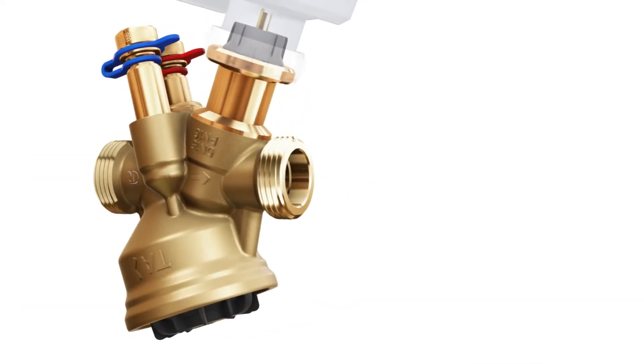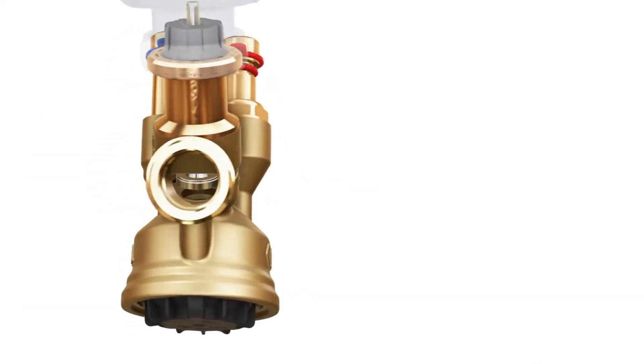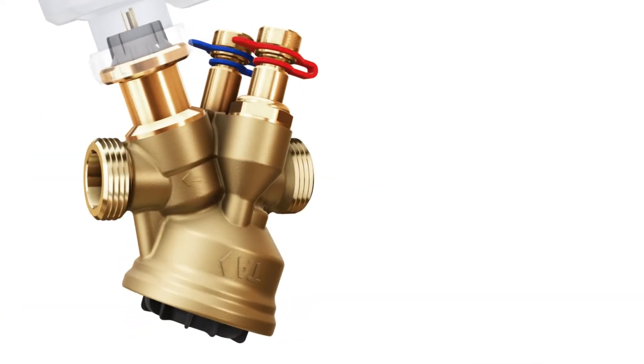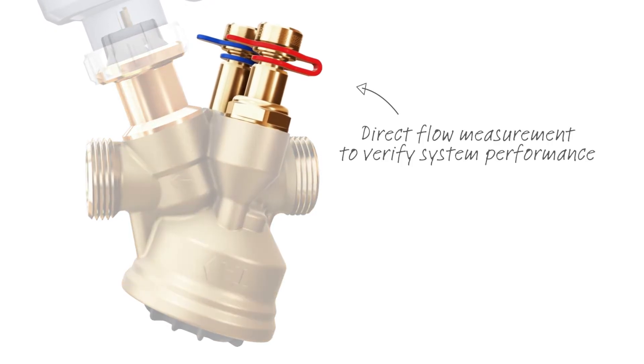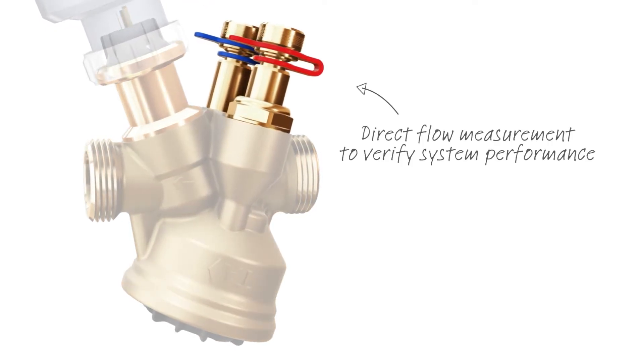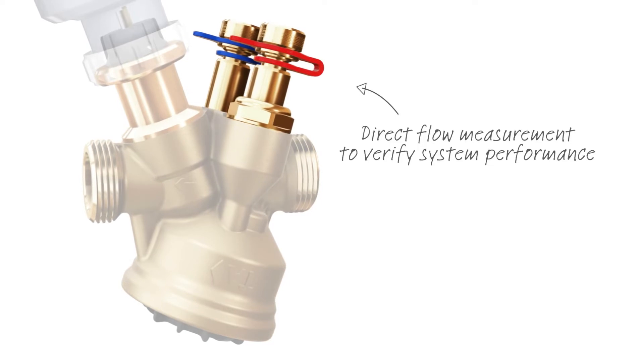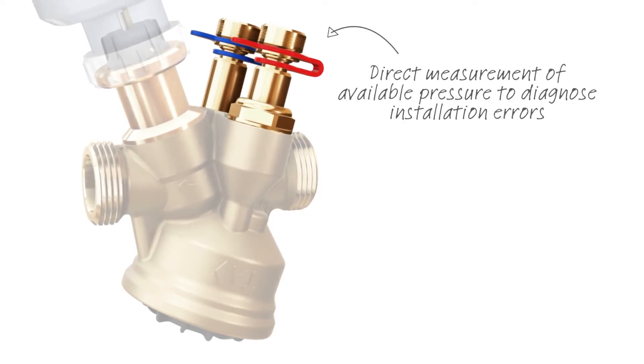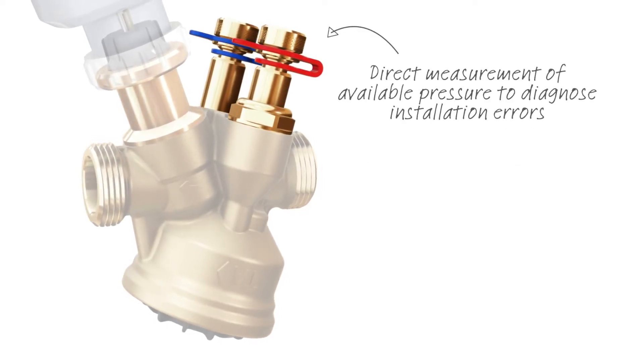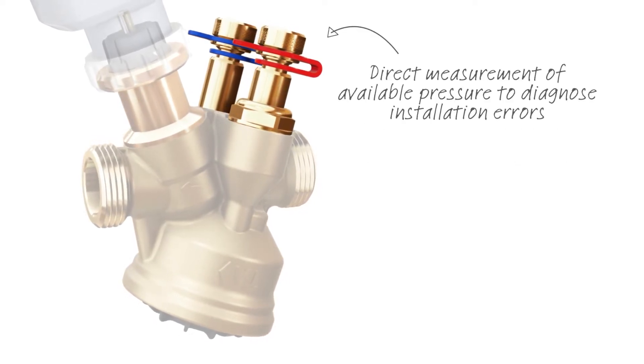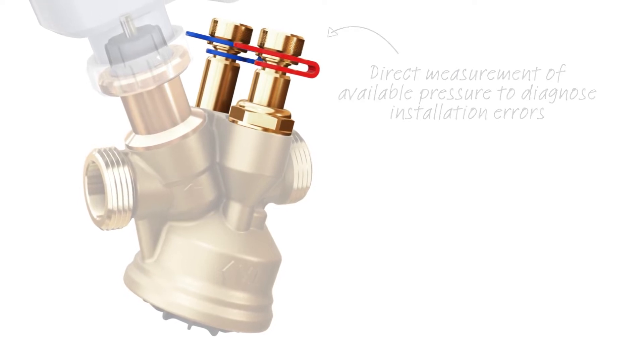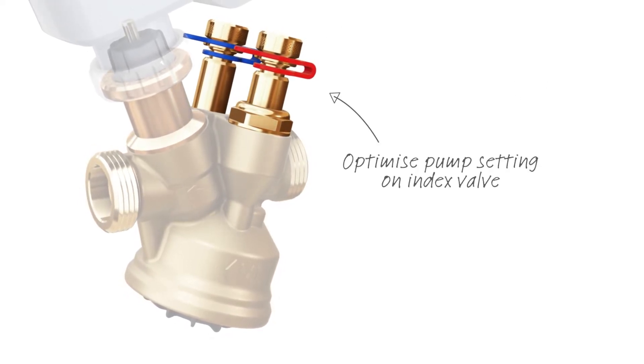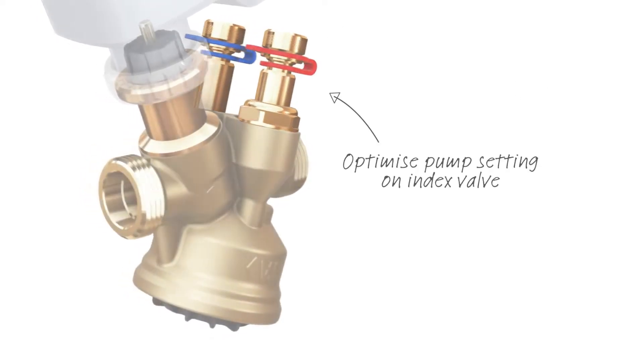With TA Modulator you can measure the true flow through the valve to verify system performance, as well as measure the available differential pressure to diagnose possible installation errors. On the index valve you can also optimize your pump setting.